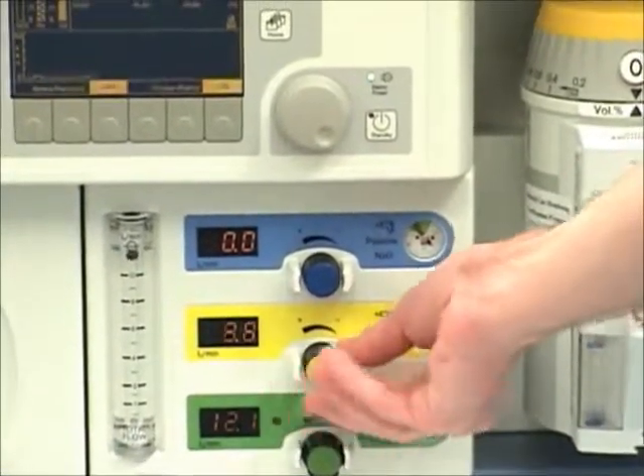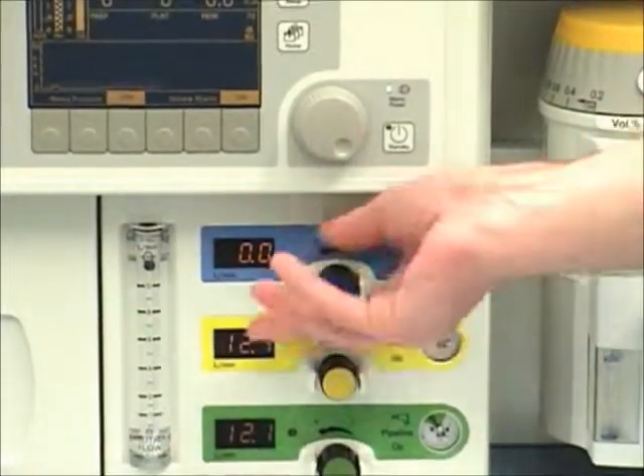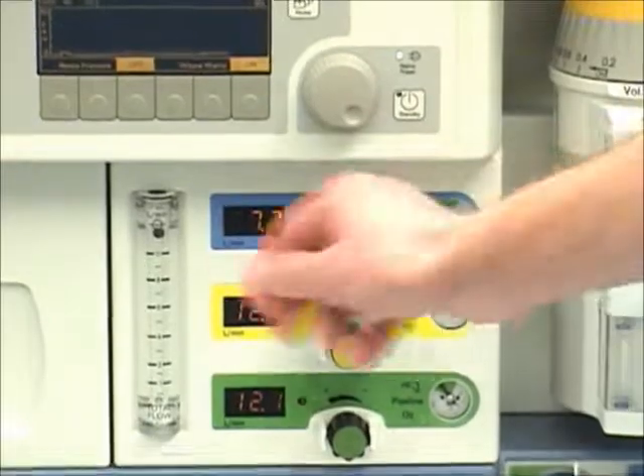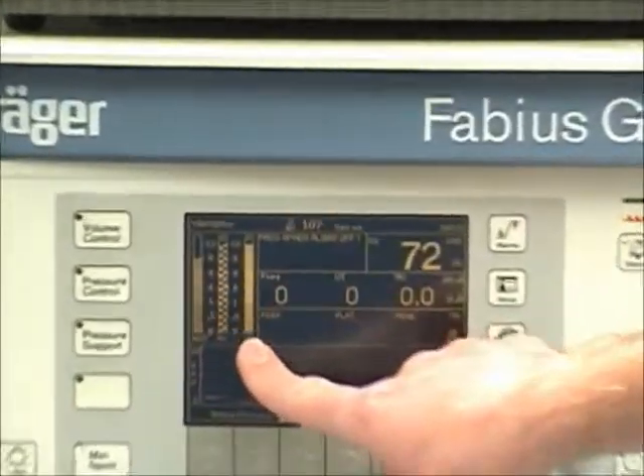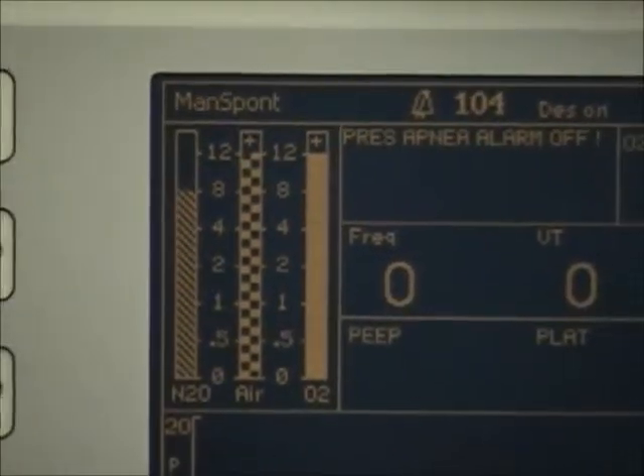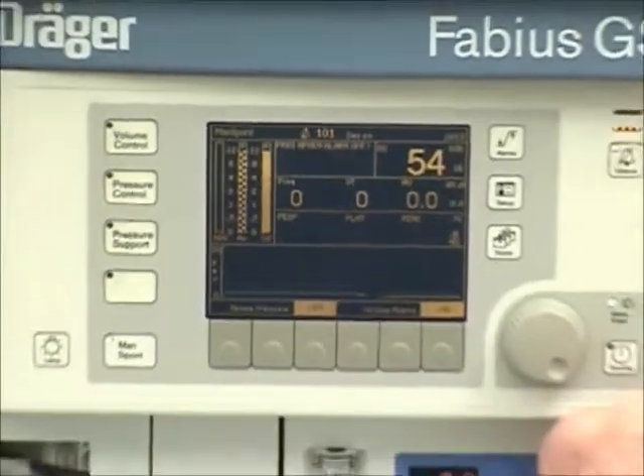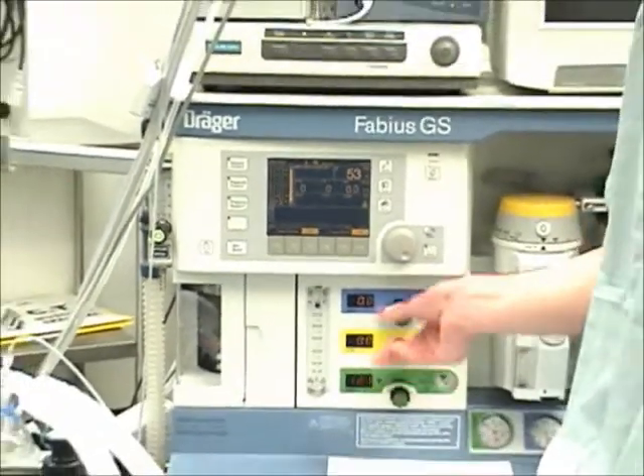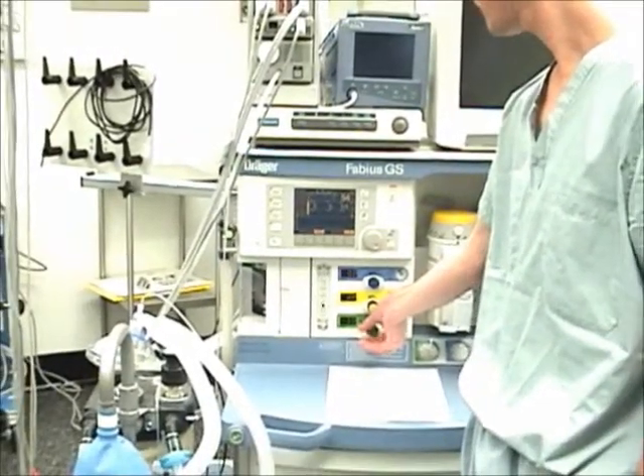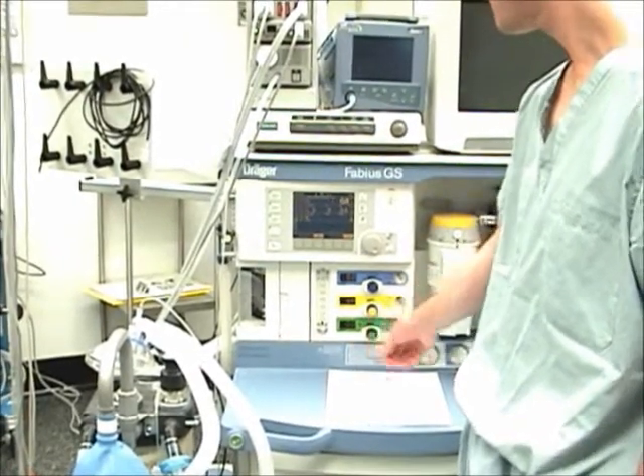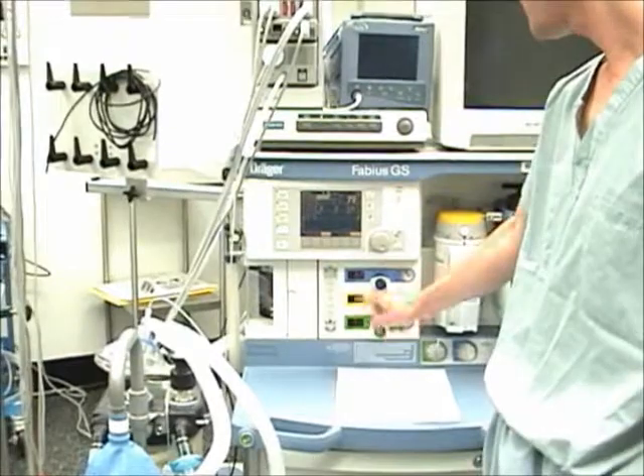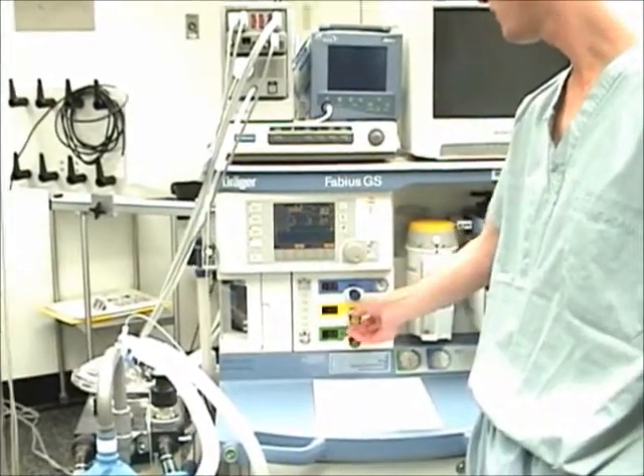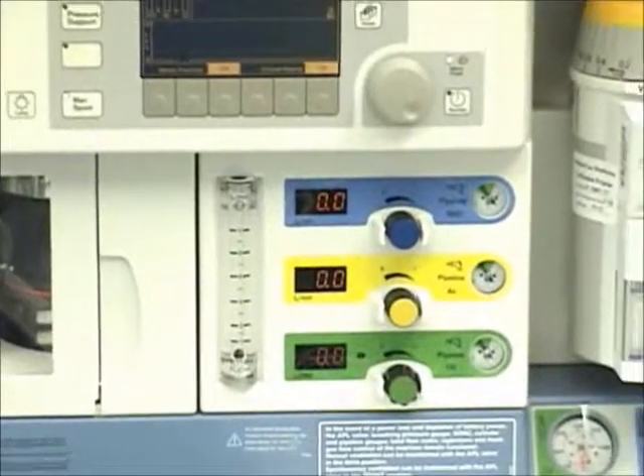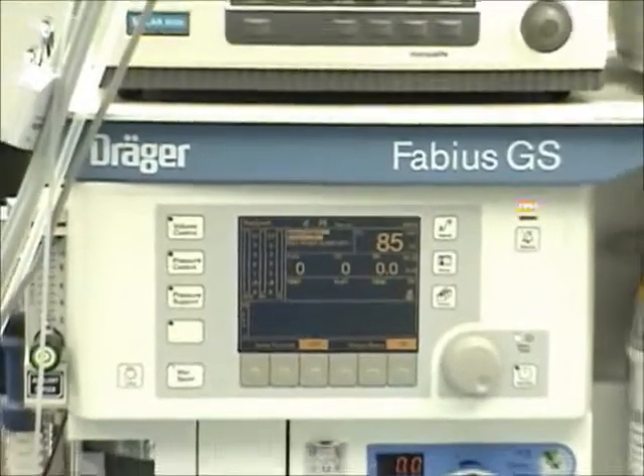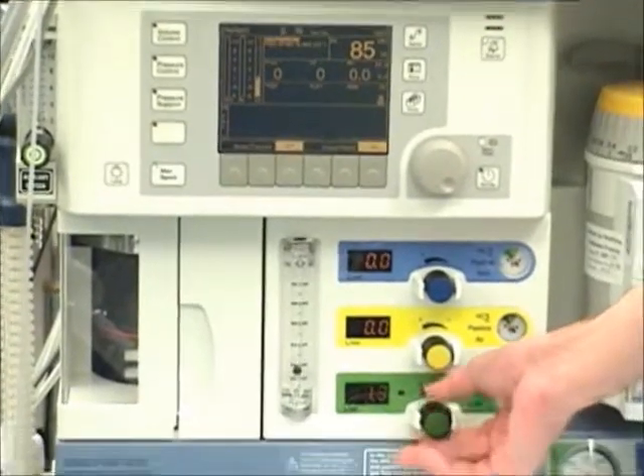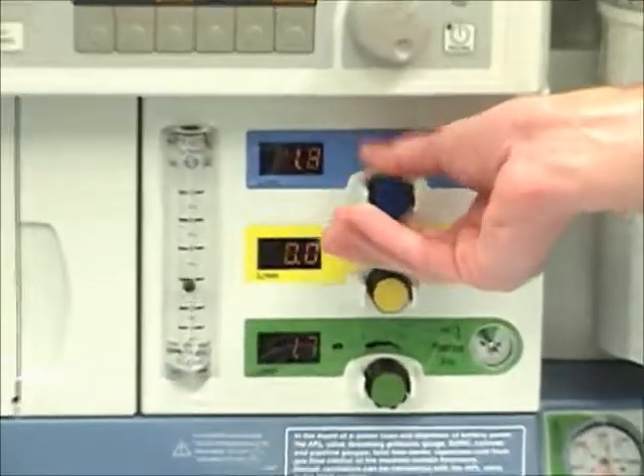Notice there is a single external gas flow tube that displays total gas flow only. Individual virtual flow tubes for each gas appear on the LED display: nitrous oxide, air, and oxygen. Discontinue all gas flow. The glass flow tube, virtual flow tubes, and digital displays beside each gas should now display 0. To assess the function of the oxygen ratio control, set the oxygen metering valve to 1.5 liters per minute and the nitrous oxide metering valve to approximately 3 liters per minute.